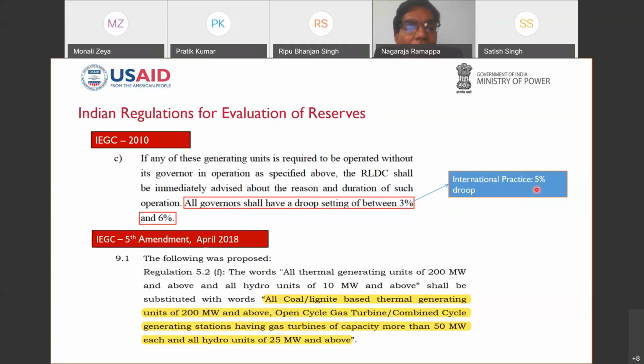And the IEGC fifth amendment, which was introduced in April 2018, talks about which generating units, and at what capacity, should participate in the primary control. For example, all coal and lignite-based thermal generating units of 200 megawatt and above should participate. Open cycle gas turbine and combined cycle, 50 megawatt. And hydro, because they have a better capability to participate, anything above 25 megawatt should participate in the primary control. Next, please.